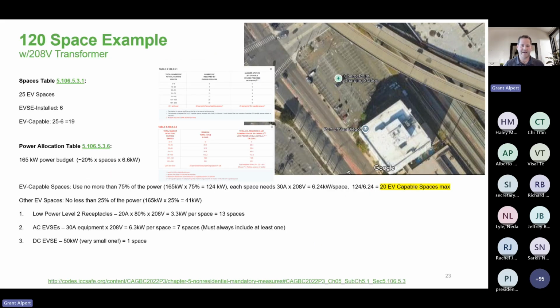And then lastly, I'm going to go over an example of a parking lot with 120 spaces and a 208 volt transformer. So this is a real screenshot from the Port of San Diego, going over 120 spaces. If we're going by the spaces table, that would result in 25 EV spaces. And from that, 6 of those spaces have to have EVSE installed.